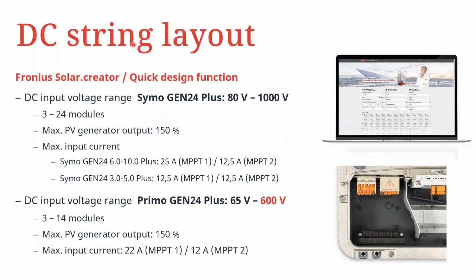But as far as the DC input range is concerned, for the Symo GEN24 Plus, this would start from 80 volts to a maximum of 1000 volts, which means that you can start from 3 modules to a maximum of 24 modules per string. And in terms of the over dimensioning, this can be done to a factor of about 150%. The maximum input currents are important to note for the Symo GEN24, 6 to 10 kilowatts. We say that we have maximum 25 amps on the first MPPT and 12.5 amps on the second MPPT. For the smaller Symo GEN24 Plus, we said we have 12.5 for both MPPTs, and therefore that difference is important to consider.